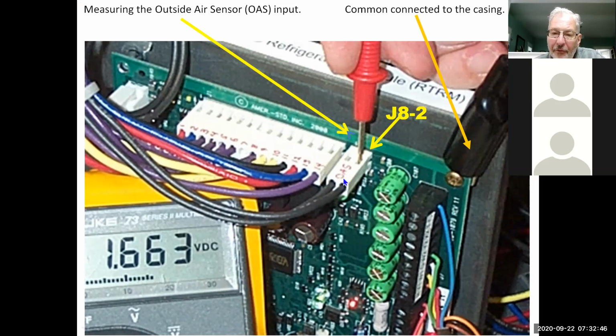But if you go to this last terminal right here, this is your outdoor air sensor. If you want to read the outdoor sensor, and by the way, they do have the pins on the top here for your meters, but it still takes a fairly small lead to get in there. J8-2 is your outdoor sensor, and that should read somewhere between 2 and 4 volts DC. The thing with DC circuits to remember is that when we're working with a 5-volt DC circuit, if it's a dead short, it's going to show 0. It's going to short out, go to 0, and the circuit's going to shut down. If it's an open circuit, it's going to show 5 volts DC. So we should see somewhere between 1 and 4 typically. If you put your meter on there and you read 1.663 volts and you go into the book, it'll tell you what the outdoor temp is reading.